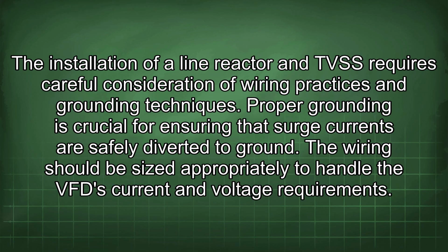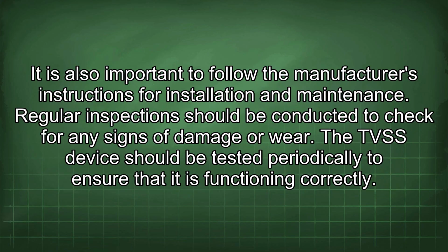The installation of a line reactor and TVSS requires careful consideration of wiring practices and grounding techniques. Proper grounding is crucial for ensuring that surge currents are safely diverted to ground. The wiring should be sized appropriately to handle the VFD current and voltage requirements. It is also important to follow the manufacturer's instructions for installation and maintenance.